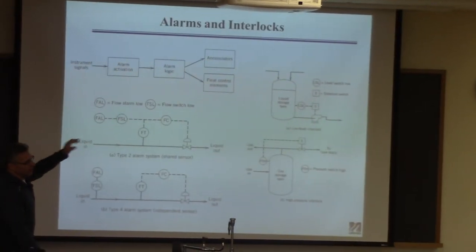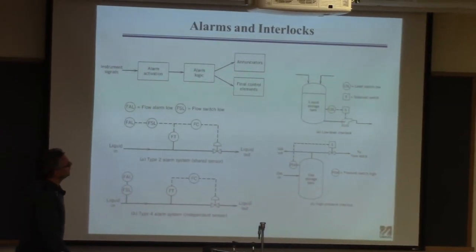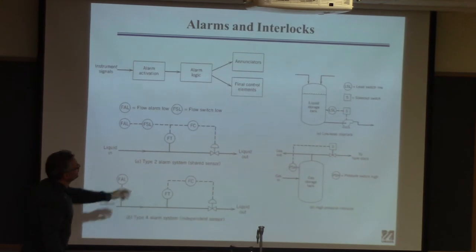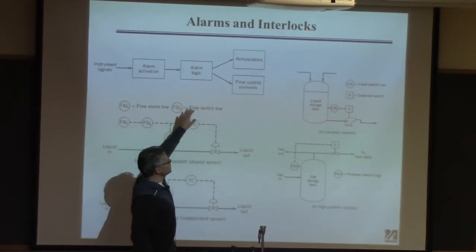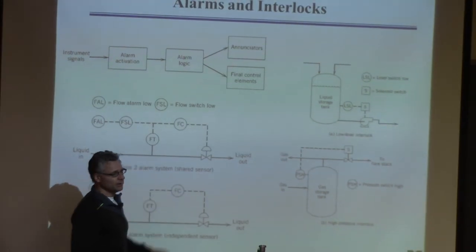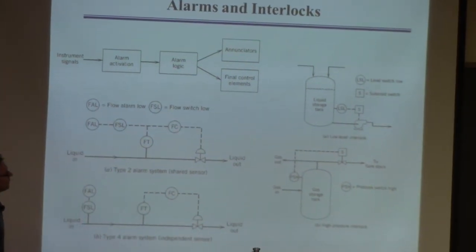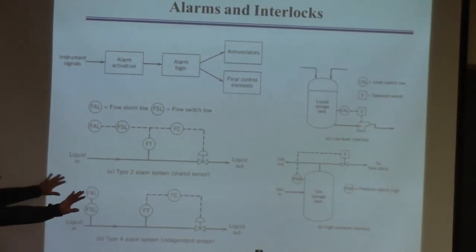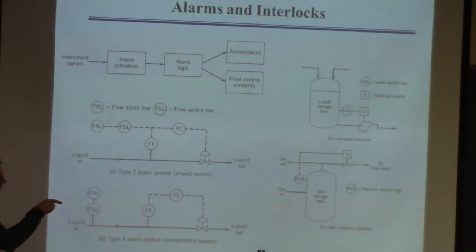Annunciators make a sound — you hear it. A final control element might actually do something as a result of the alarm, like high pressure: maybe just open a valve and vent. You always have these alarms going off so people know, because there's too much information to see on the screen. The idea of the alarm is to draw immediate attention to what the problem actually is.